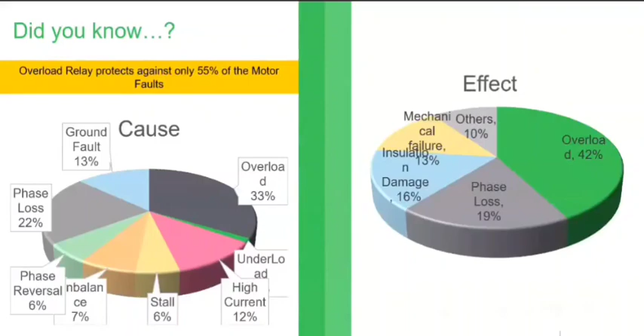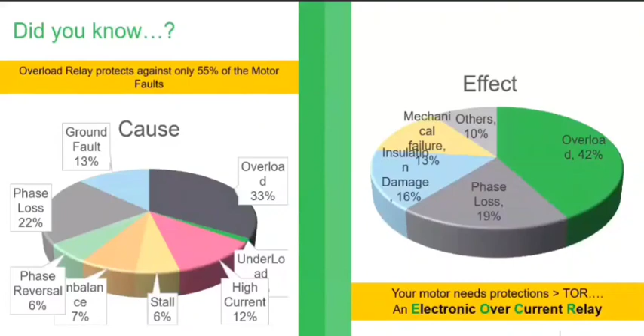Also, a thermal overload relay is a thermal sensing device. It is not a current protection device, due to which if any current surge, leakage current, or any current due to a short circuit prevails, your relay is not designed to check that short span of current surge. That is the reason we needed an electronic over current relay, which is a current based protection. It will take care of your thermal overload as well as your current based protections.